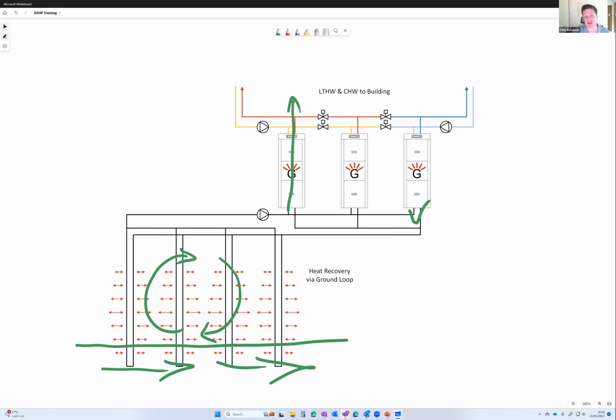Just to give you a bit of an understanding of how these things work in practical terms in the building, I've got one heat pump cooling, as I said, so we've got these two valves here shut and these two valves here open. If our cooling load was to increase and our heating load decrease, then we would now close these two valves here, and we'd open these two valves, and we would reverse this heat pump. So we'd then have two heat pumps cooling and one heat pump heating, and we can flip-flop either way.